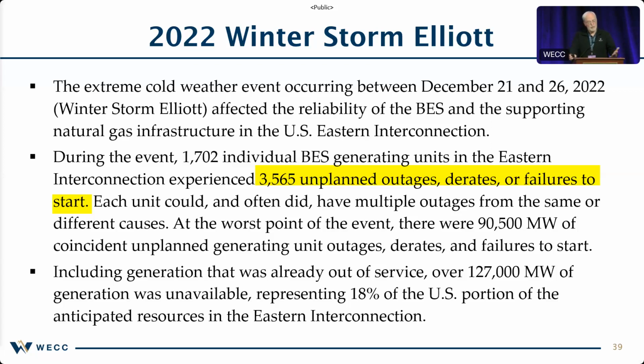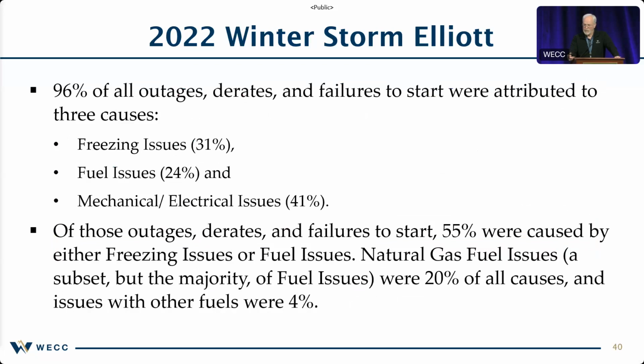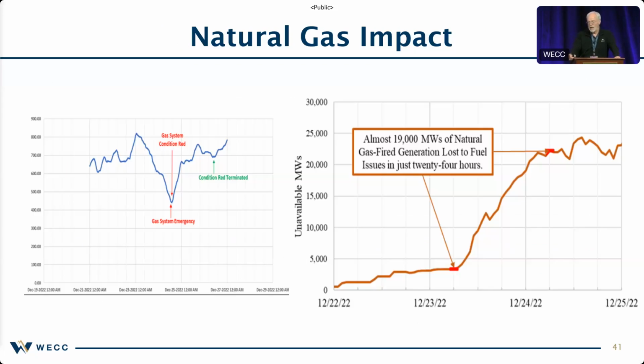And so those neighbors that had emergency power available started supplying that power to the individuals that were having the problems, at least the ones that started losing the generation first. There were 90,500 megawatts of generation loss during this event. So out of that, 96% of them, 31% freezing issues, 24% fuel issues, 41% mechanical electrical issues, and natural gas impact. So we see here on the left, this is the natural gas pipeline.